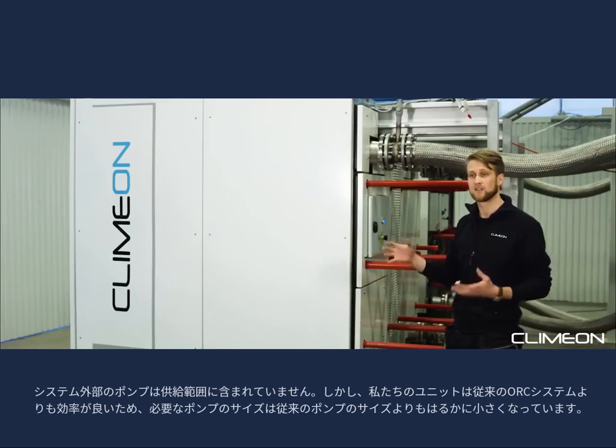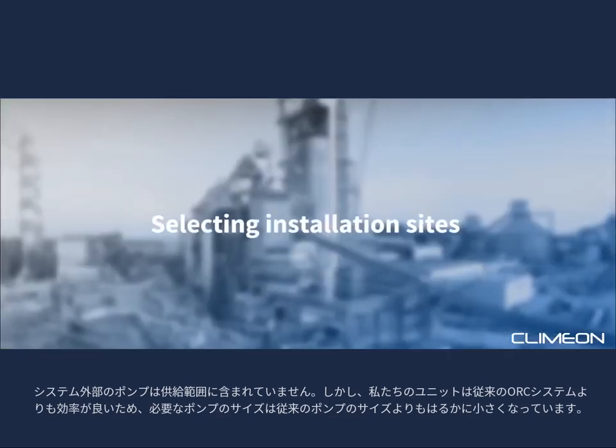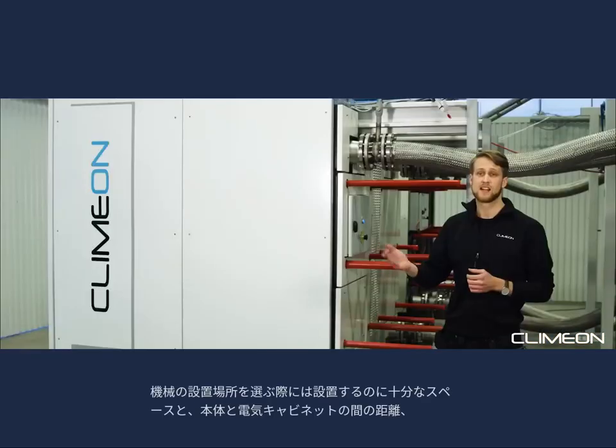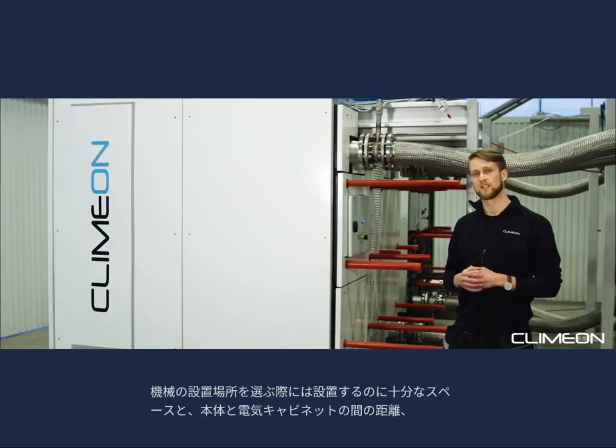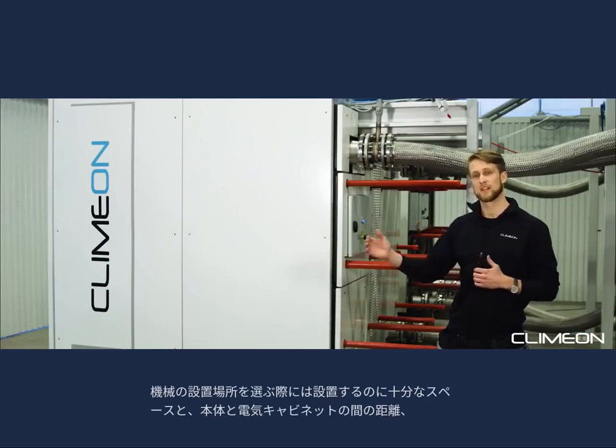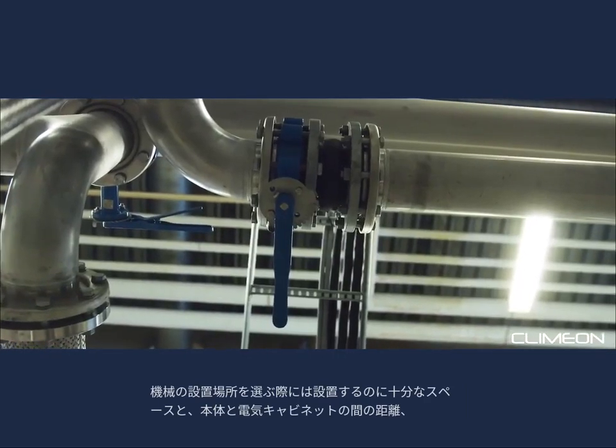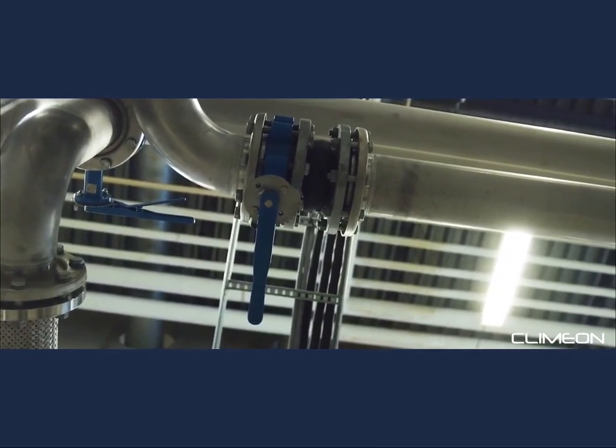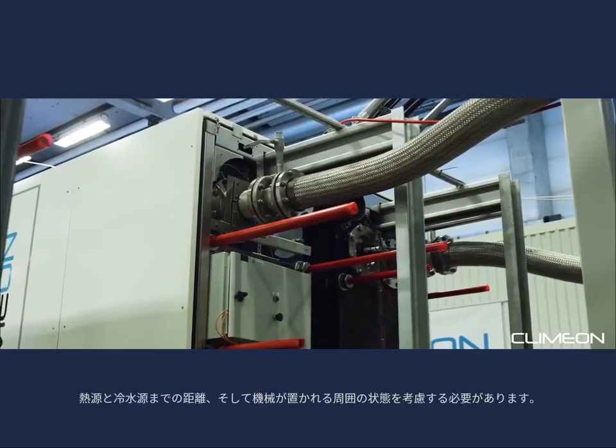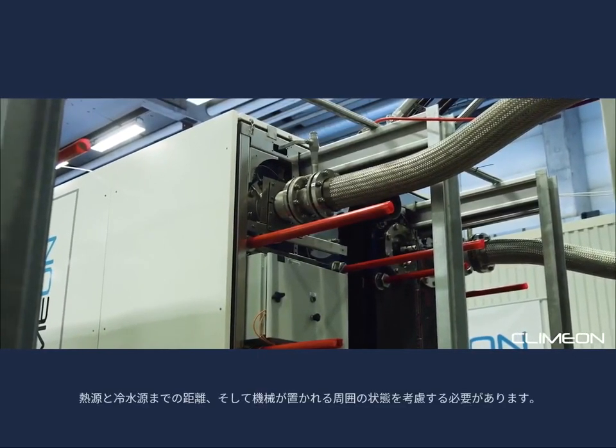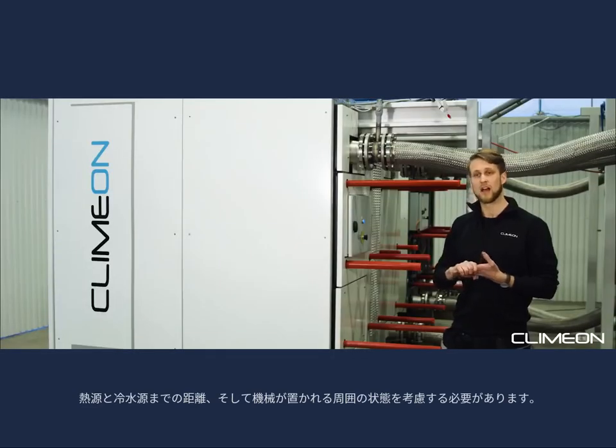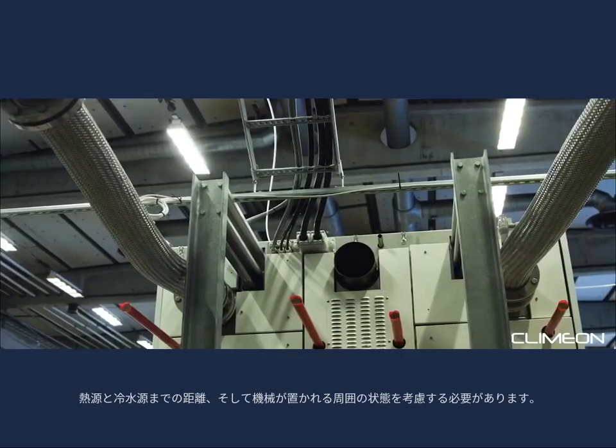However, the size of the pumps you need for our units is a lot less than you would need for a traditional ORC because it's more efficient. When choosing a site to install the machine, you should consider the service area needed in front and in the back of the machine, the distance between the main unit and the electrical cabinets, also the distance to the heat source and to the cooling source, and also the ambient conditions in which the machine will be placed.